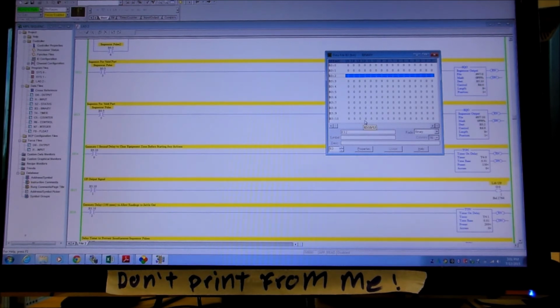Now when we put a valid part on, that's this register here, register 10, and we can see again the different steps over here, and then the different bits that are switching over here. And our part's in, it's going up. It's making measurements, and now it's activating the control valve, and now it's just waiting till we complete, and when we're finished it'll go back to all zeros, and there we have it, and we're back at step 1, and that's the way the sequencer works.